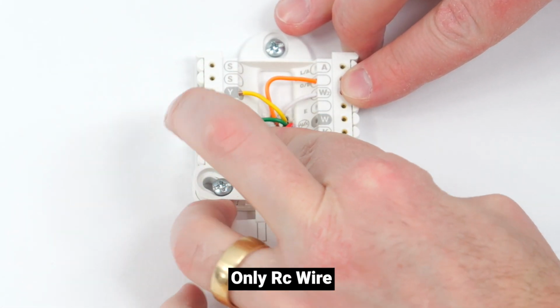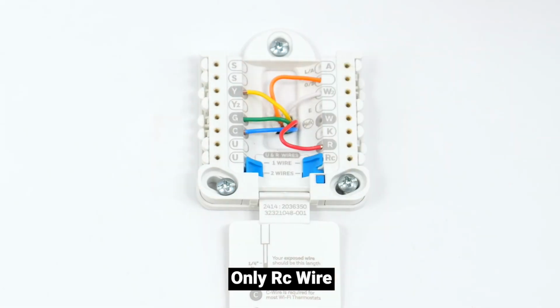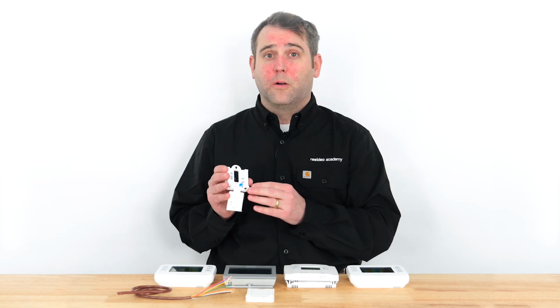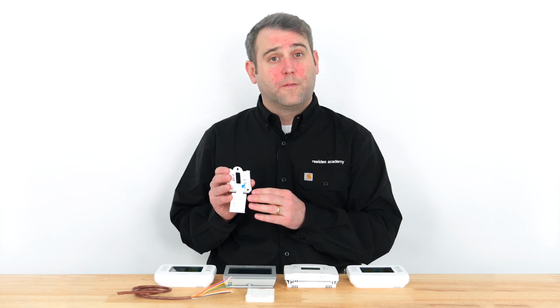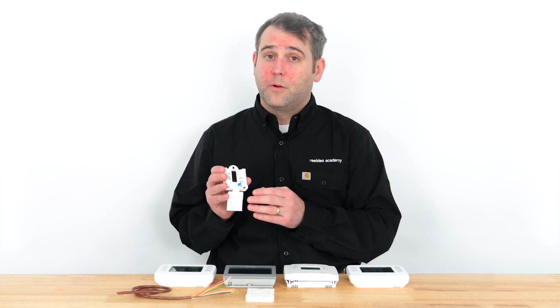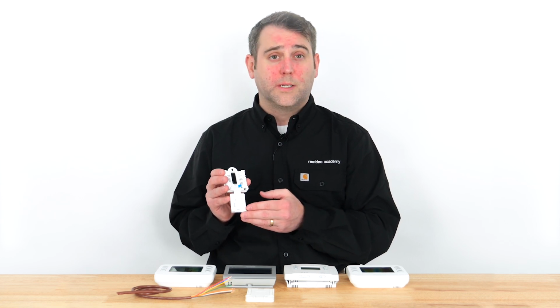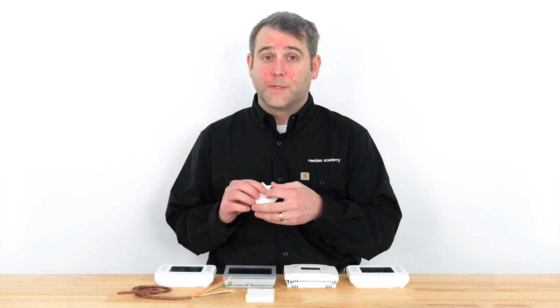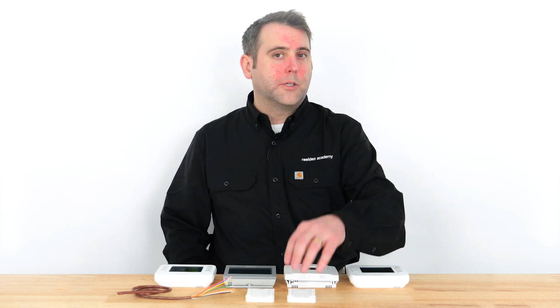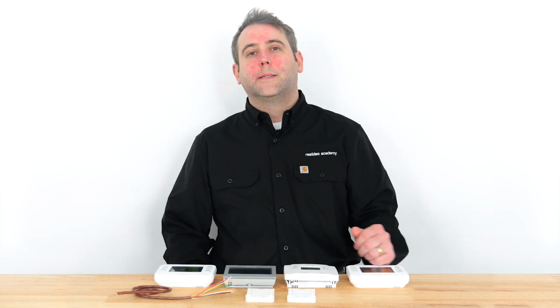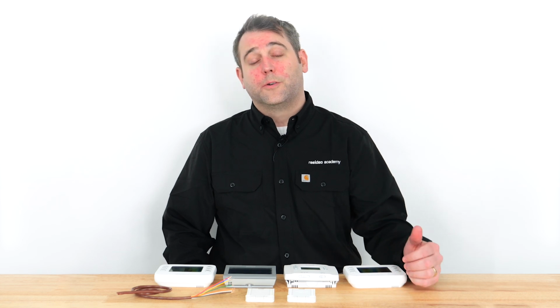If you have an RC wire, but no R wire, you'll move the RC wire to the R terminal and move the jumper switch into the up position. If all your wiring appears correct and secure, confirm your thermostat is configured for your system type. Refer to your thermostat installation instructions for more details. If you're replacing your thermostat because the previous thermostat wasn't operating your heating, the problem may actually be in your HVAC system. Contact an HVAC professional to troubleshoot your system.